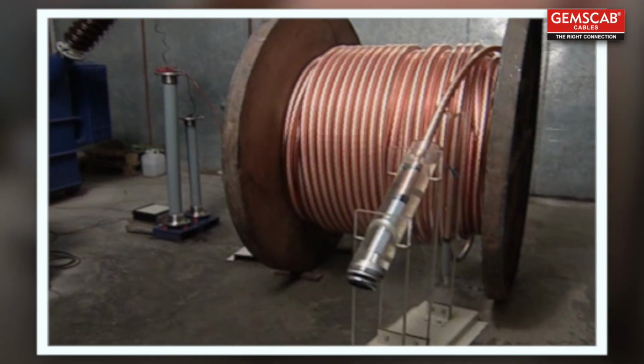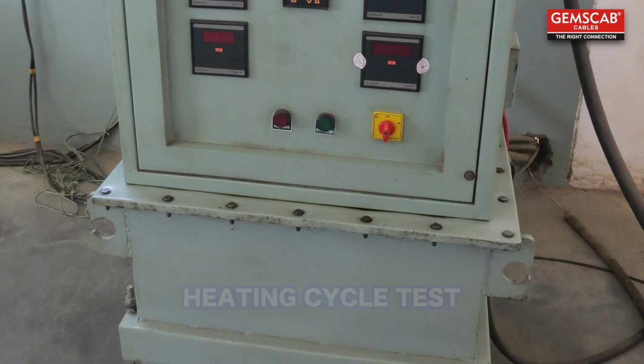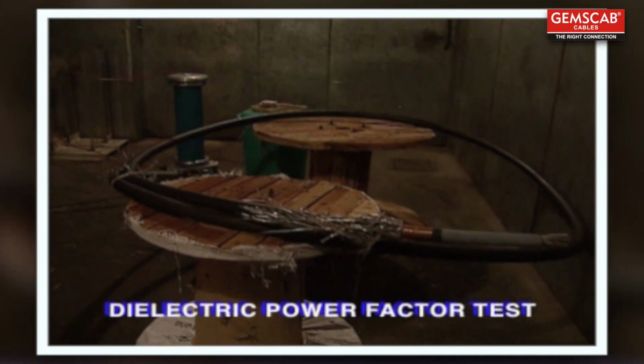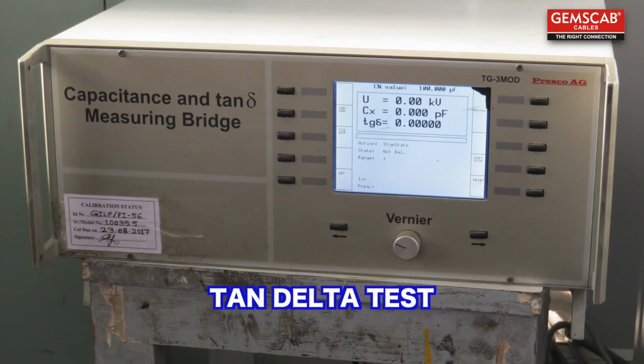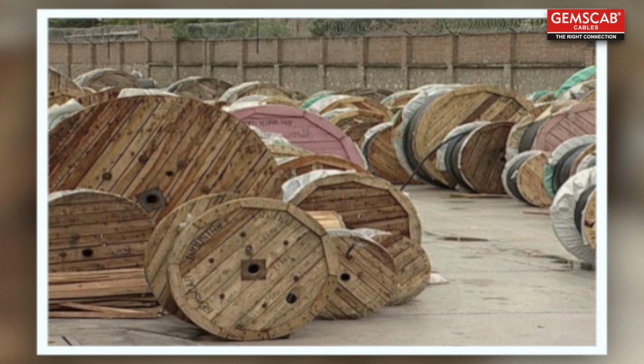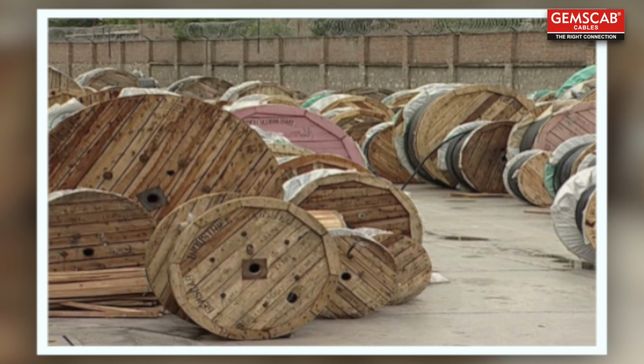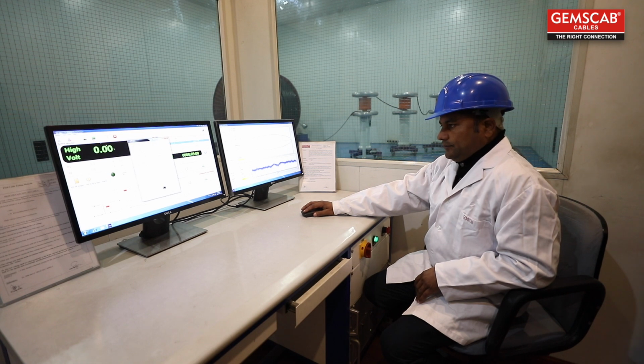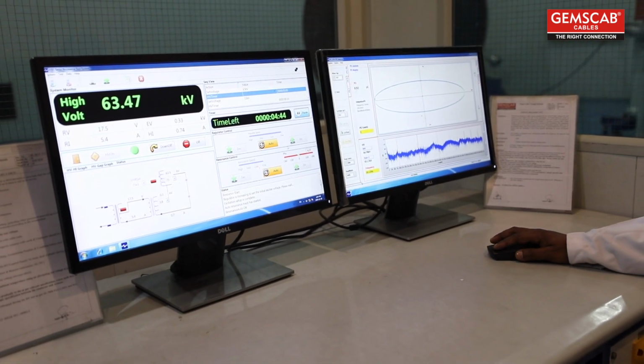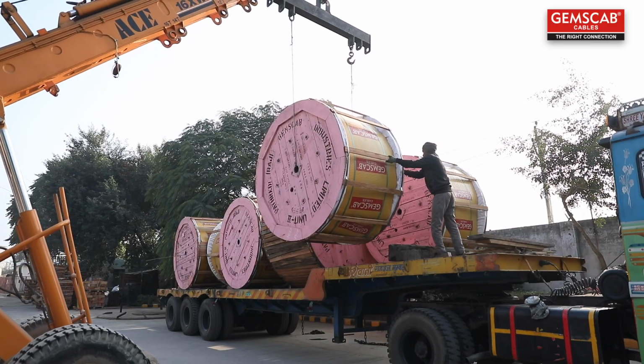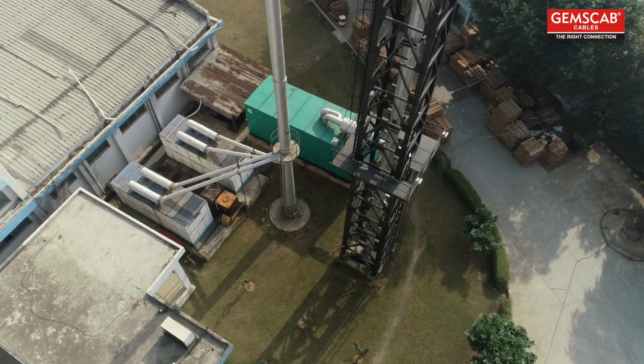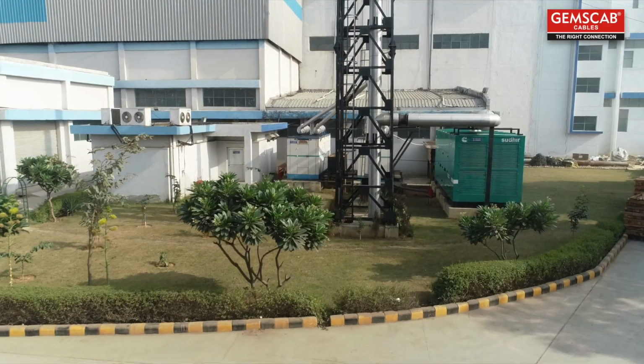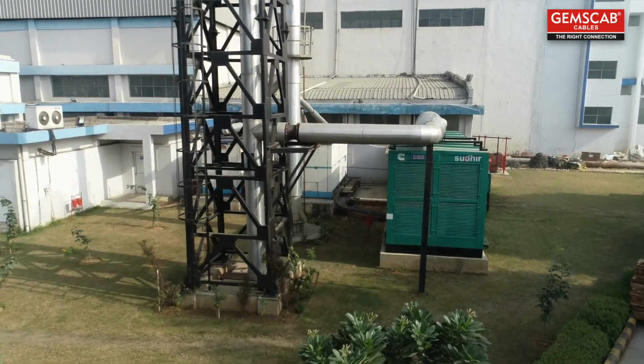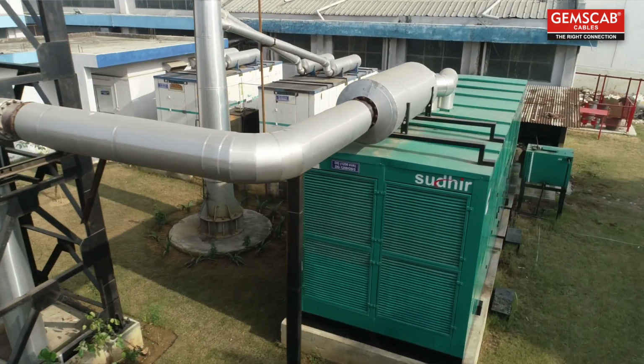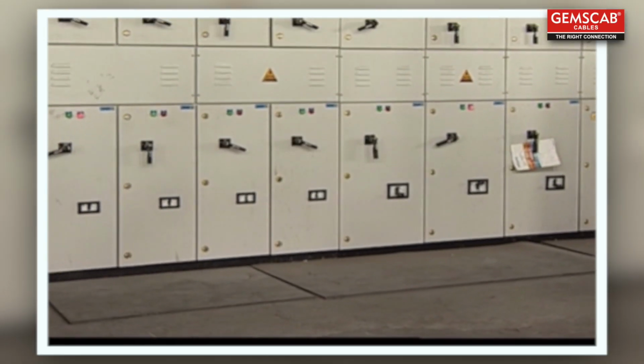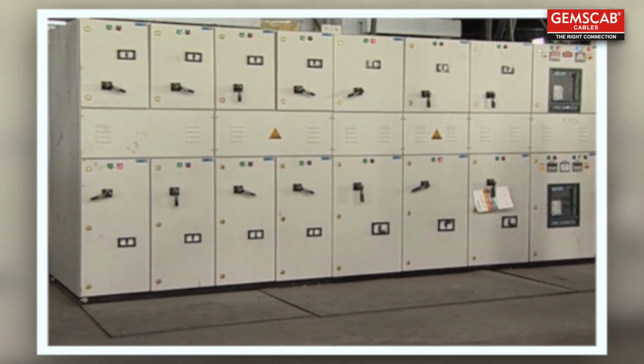Additional tests conducted on HT-XLPE cables include the partial discharge test, heating cycle test, dielectric power factor test, impulse test, and tan delta test. Gemscab has all in-house facilities for type testing for LT and HT cables. Test lab is equipped with 2 partial discharge test equipments, one for routine testing and another for final testing. Only products conforming to outlined design parameters and quality standards are released for dispatch. To avoid process variations and faults due to power failures, the Gemscab plant is equipped with a DG power backup of 4250 kVA with an additional 1650 kVA UPS exclusively meant for extruders.